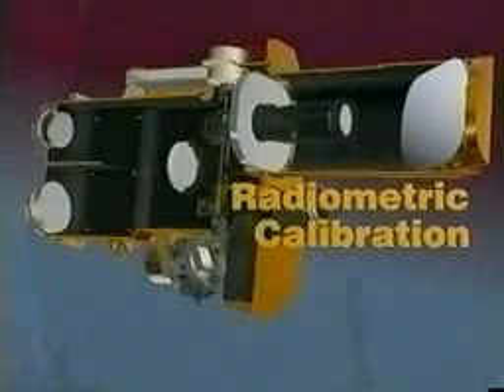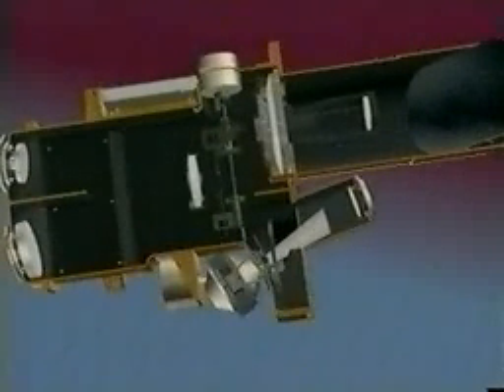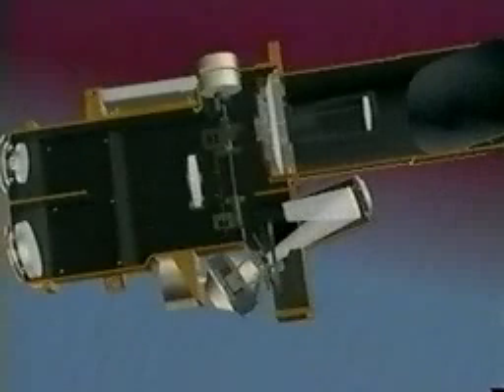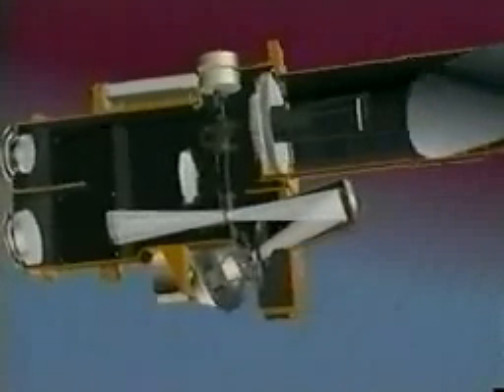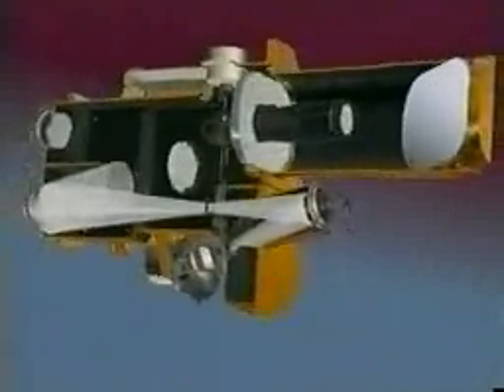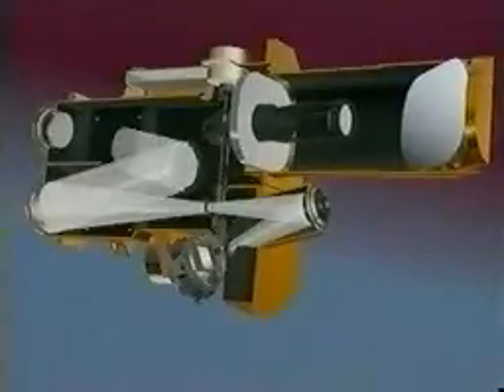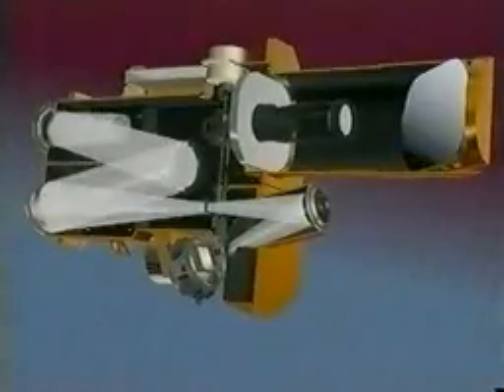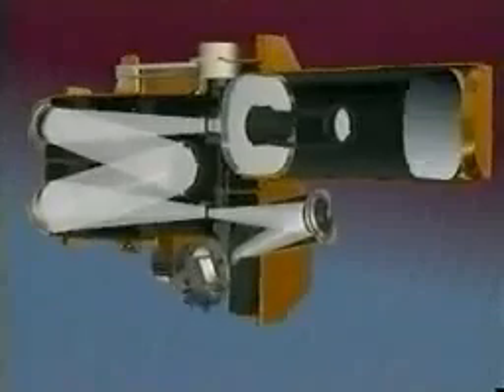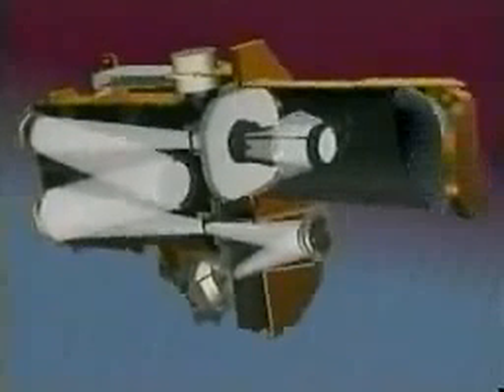Radiometric calibration is accomplished using light generated by the spherical integrating source, or SIS, which passes through the open position on the source filter wheel and through the monochromator via a plane mirror positioned in place of the diffraction grating. The light exits the monochromator, passes through the collimator, and onto the exit fold mirror, which reflects the beam out of the SRCA and onto the scan mirror.